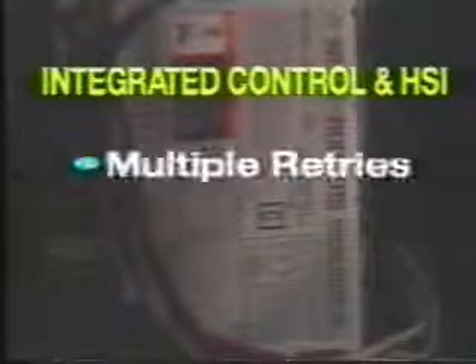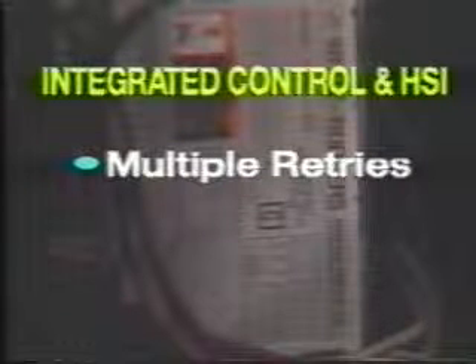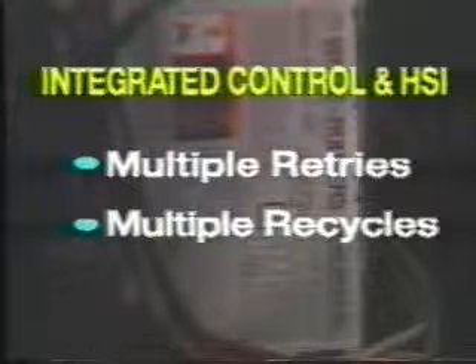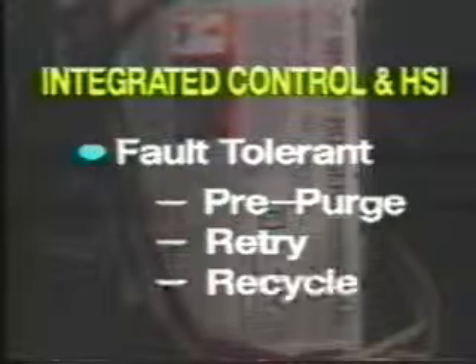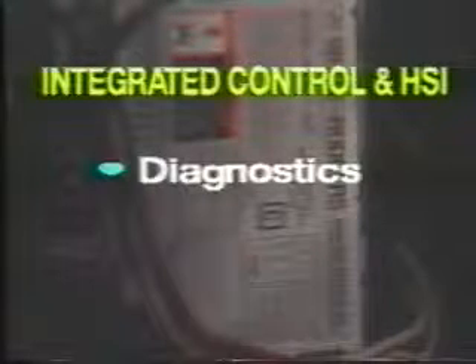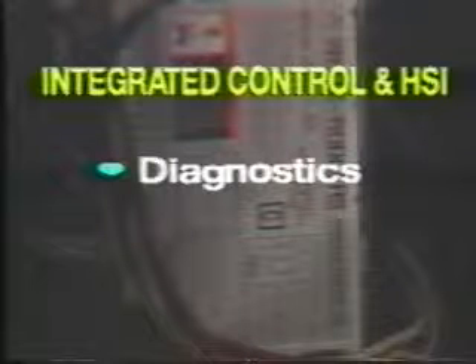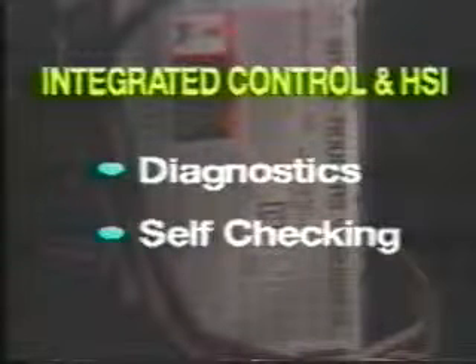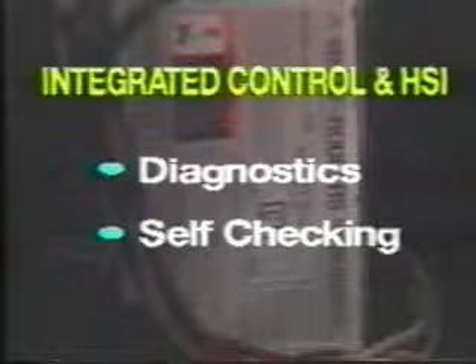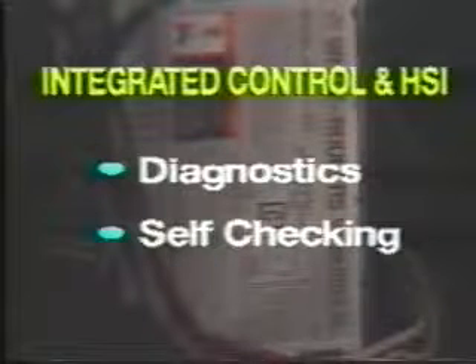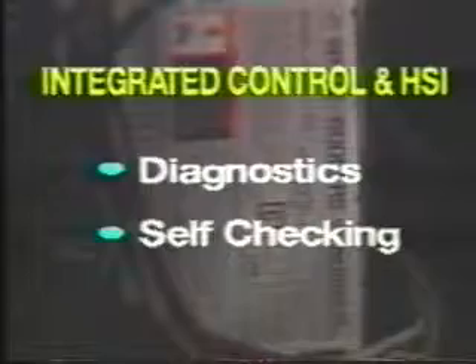The integrated control keeps many of the ignition features of the White-Rodgers HSI system and adds some new ones. Remaining from HSI are multiple retries after a failure to ignite, multiple recycle attempts on flame loss during normal burner operation, fault-tolerant circuitry for pre-purge retry and recycle, and multiple external diagnostic codes. For added safety, the microprocessor performs an internal self-check of its own operation and the proper operation of all external safety and control switches. This check is repeated more than 16 times each second throughout each heating cycle.